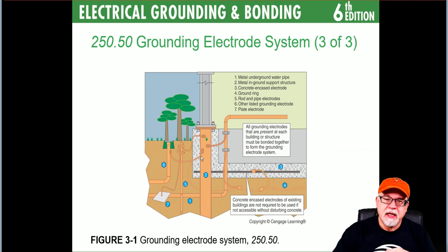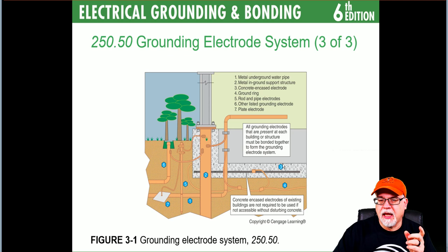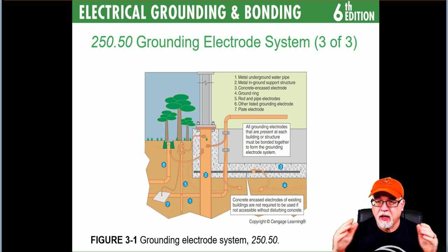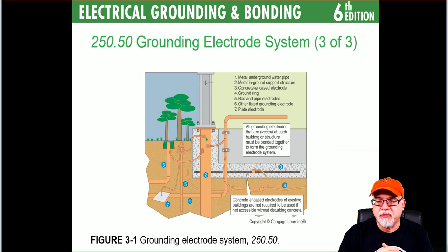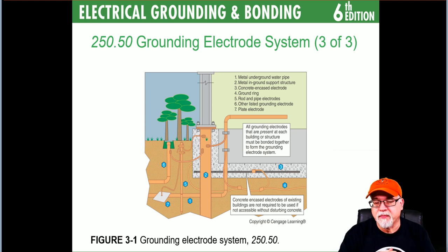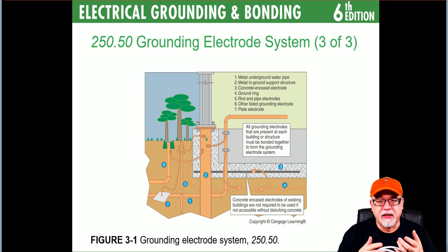The third type is the concrete encased electrode — 20 feet of half-inch rebar in the footer in contact with the earth or foundation. It has to be at least 20 feet, but doesn't have to be continuous — pieces connected together with tie wires can cumulatively make up more than 20 feet. The other option is four-gauge copper placed in the footer, also requiring 20 feet.